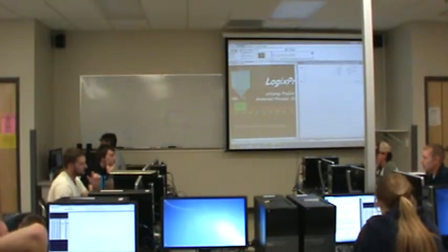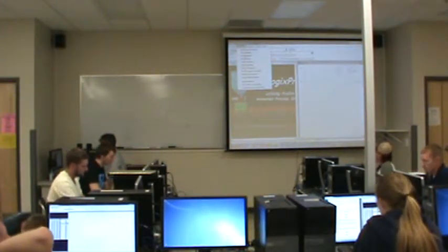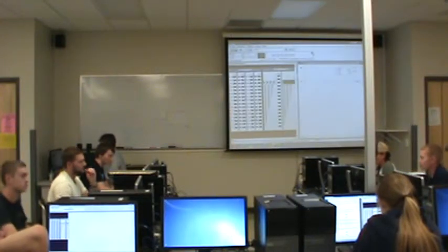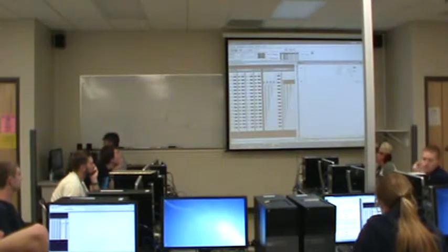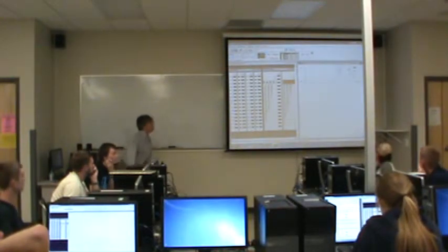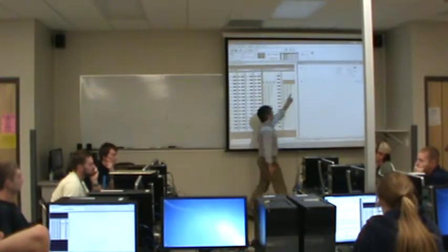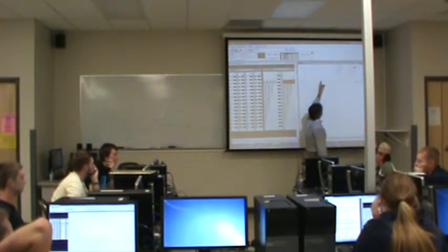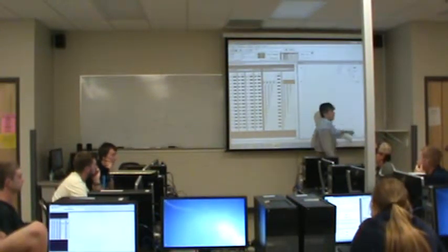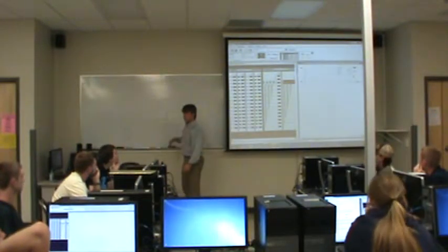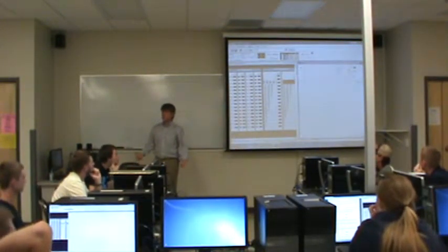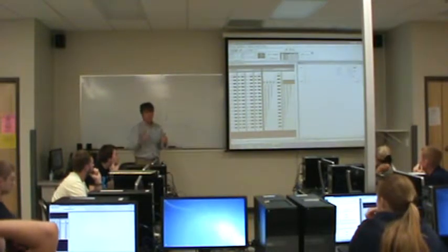Now let's play with this just as it is. Like I said, what it's going to do when I run this is simply increment its count by 1 and sit there. Why? Because the preceding rung up to the instruction is true. And so all it has observed is that the program started, therefore there was a transition from off to on. So it's just sitting there waiting for the falling edge before it counts another rising edge.